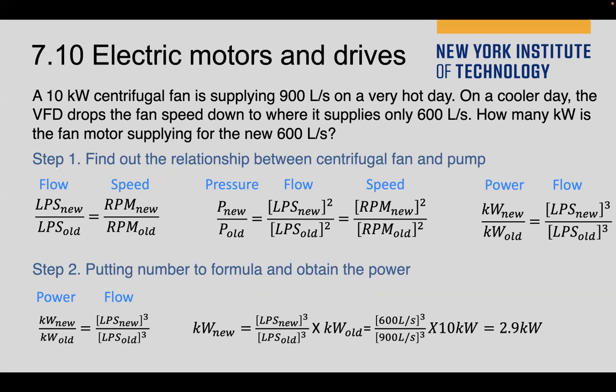A 10 kilowatt centrifugal fan is supplying 900 liters per second on a very hot day. But on a cooler day, the VFD, variable frequency drive, drops the fan speed down to where it supplies only 600 liters per second. How much power is the fan motor supplying for the new 600 liters per second?